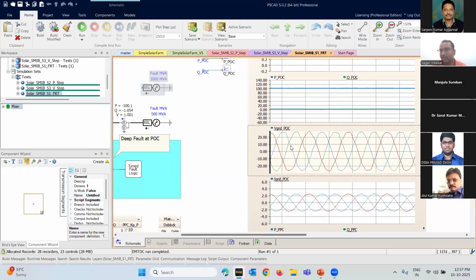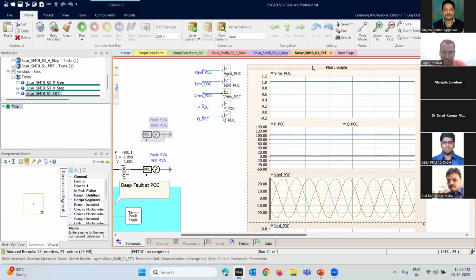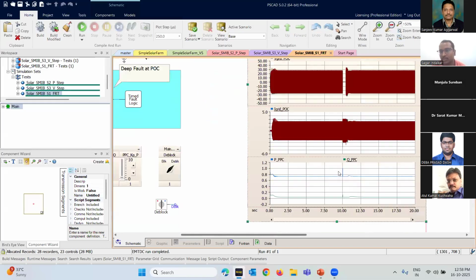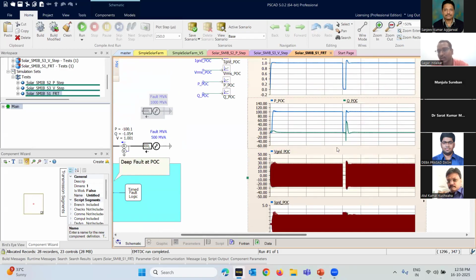Now here you can clearly see the harmonics, right? This is not a pure sine. If I perform a fast Fourier transform of this waveform, I get to see the harmonic contents individually. This is possible in PSCAD. And then the inverter was able to withstand that event.